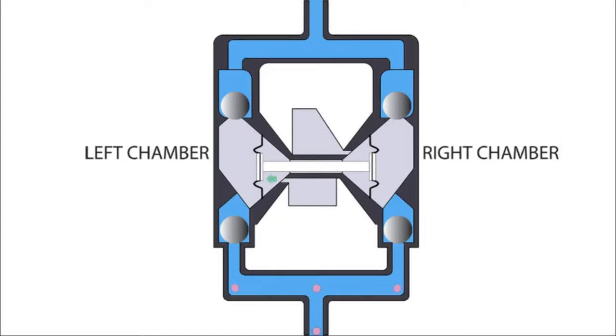The air valve directs pressurized air to the back of the right diaphragm. This begins left chamber suction stroke, which starts as the left diaphragm is moved toward the center of the pump, thereby creating a vacuum in the left chamber. Atmospheric pressure then forces fluid into the left chamber through the inlet ball valve.